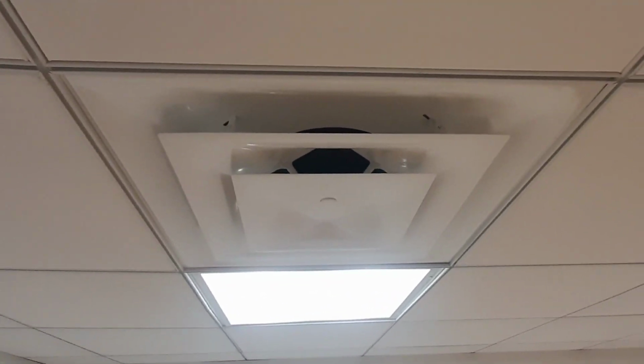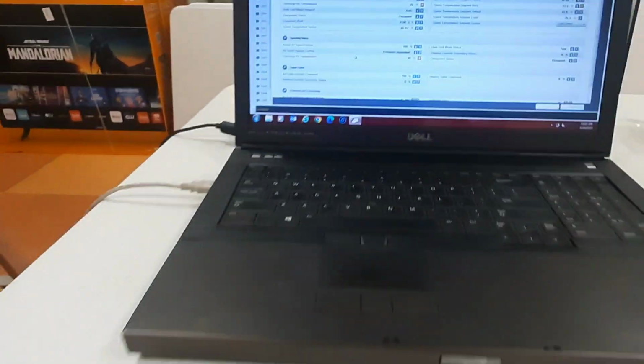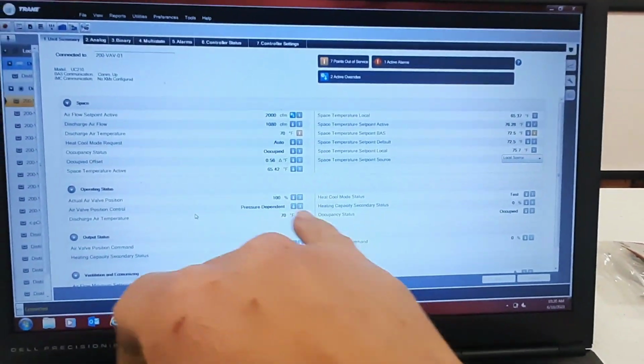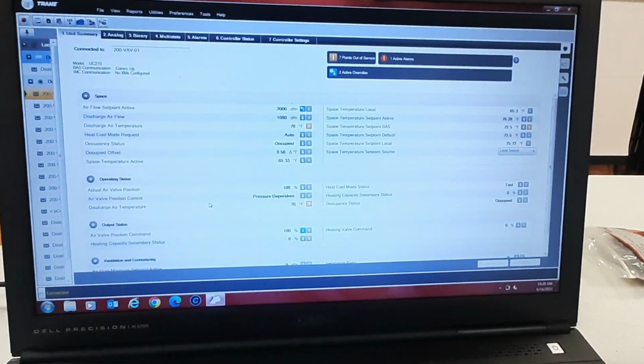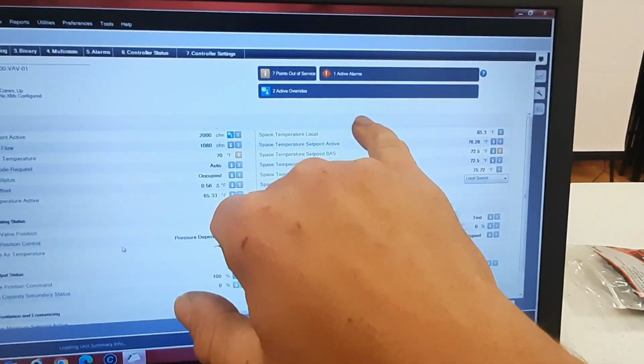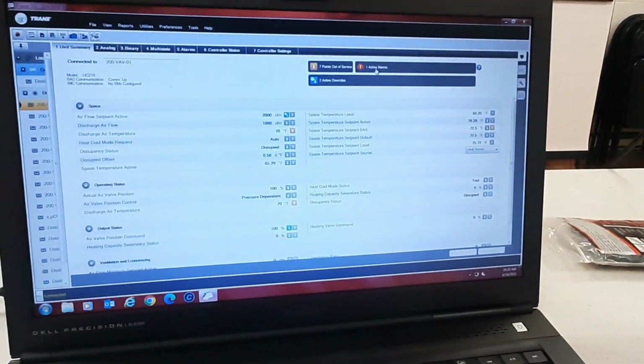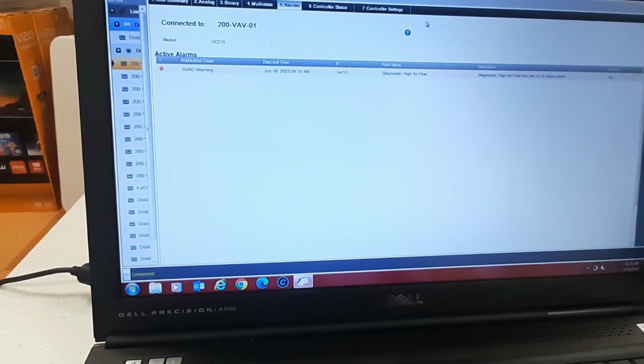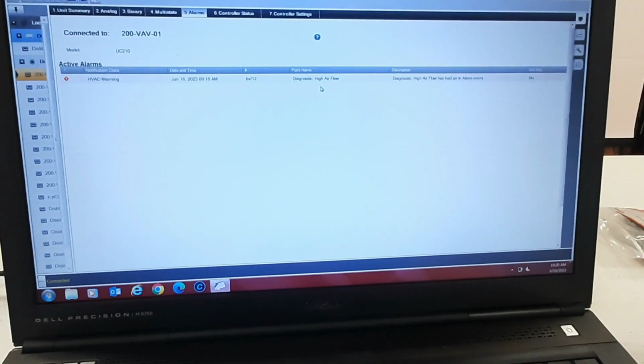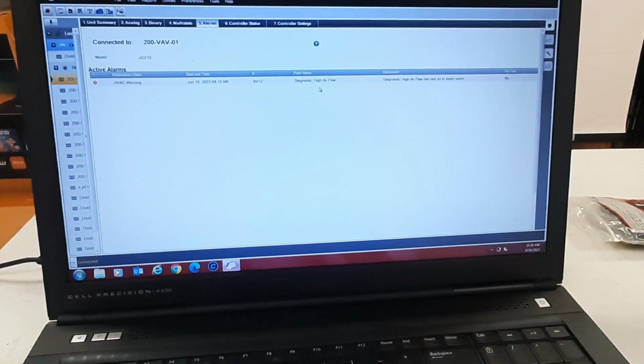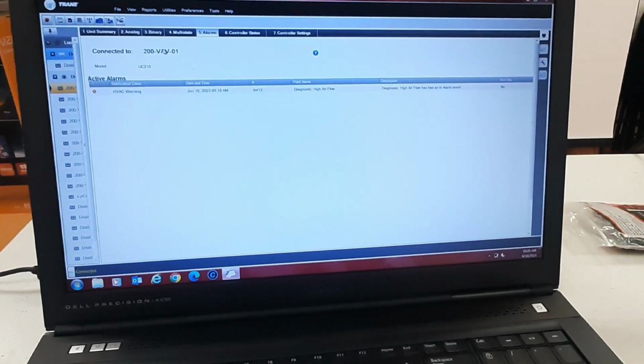And that's not overly noisy. Sounds good. And I can feel the airflow, so that's good. That's a start. At least I got it to do something. So let me go in here and figure out why my set point active was 0 and what alarm popped up. I don't know what that is. It's new. Oh, high airflow. I'm guessing that's because it's going over my max airflow setting, so no big deal there.